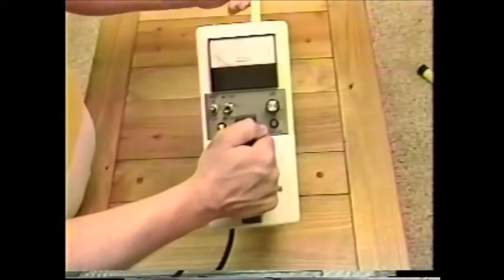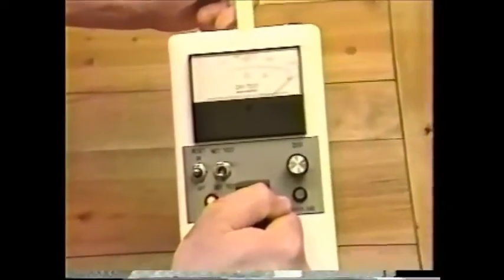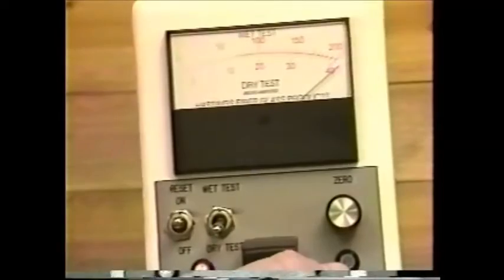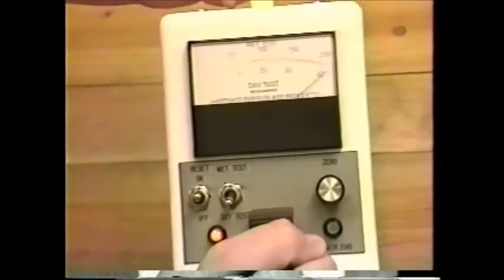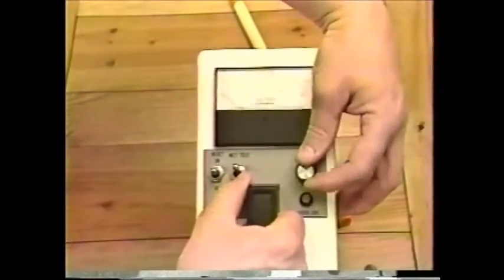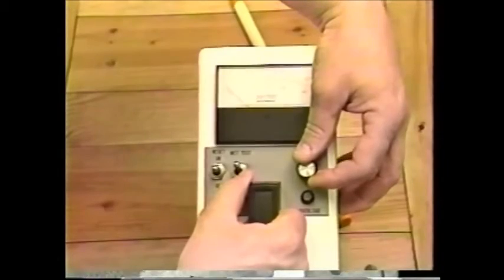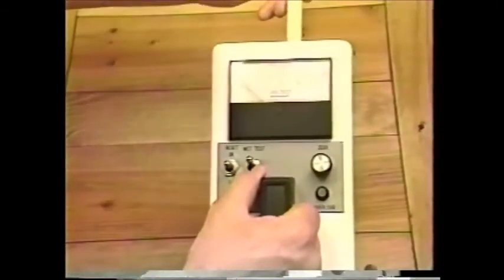When the dry scale is selected and zeroed, a full scale reading should result when the test bar is inserted. When the wet scale is selected, an indication of between 25 and 50 microamps will result.